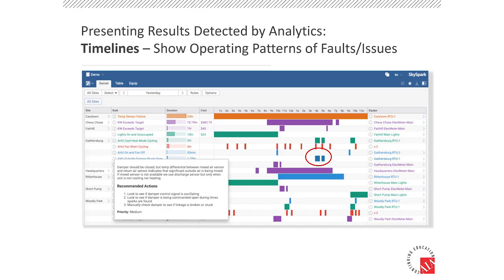And this is a big area of development by all the companies involved in analytics: how do we communicate information to human beings as intuitively and effectively as possible? One technique we use is called timelines. What we're seeing here are not on-off equipment timelines, but fault timelines. KW exceeding target, when it began, when it ended, lights on during unoccupied period, short cycling of equipment, damper stuck open when it shouldn't be.